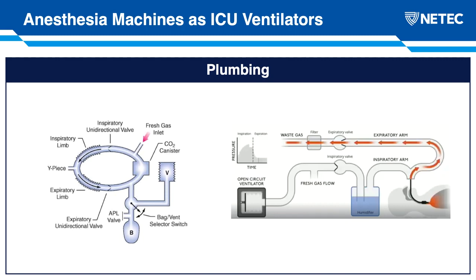And the first thing I wanted to talk about just very briefly here, and we'll hit it a few more times over the course of my slides, is the difference between a traditional ICU ventilator we see on the right and an anesthesia system on the left. As we know, on the right, in our traditional ICU ventilators, we get fresh gas, we pressurize it, we usually humidify it, and then we pass it to a patient's lungs. And it's a one-way system. So once we exit the patient lung, that exhaled breath moves in a one-way fashion along through the expiratory valve, is typically filtered, and makes its way out into the room.